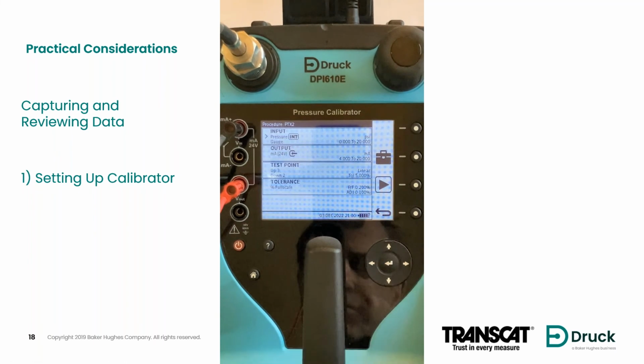Paused it. What we're looking at here is, you can actually set up a procedure on the unit itself where you define the input, the range of that input. You'll see here I've defined it as 0 to 20 psi. The output is 4 to 20. You can define the number of test points, and then the tolerance, where you have 2 tolerance measurements. One is a pass fail and the other is an adjustment. So I've set it at 0.2 and 0.1 respectively. So that's the first step of setting up a procedure that's saved on the calibrator itself.